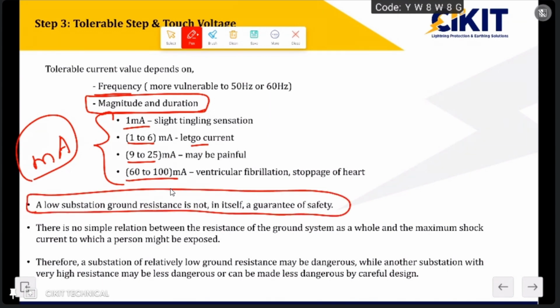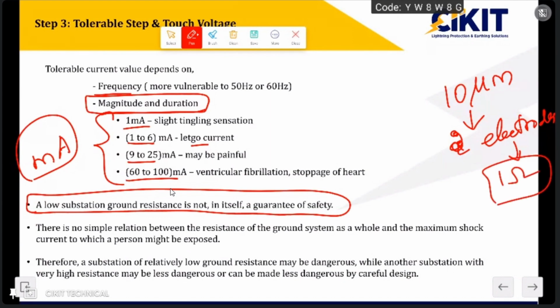For example, if I'm working with some substations, they will tell that if you provide two earth electrodes for body and two earth electrodes for neutral, that will be sufficient for the protection. If earth electrode resistance is the only parameter, and I'm working with site conditions having a resistivity of 10 ohm meter, then if I install only one or two earth electrodes, I can achieve a resistance value of 1 ohm. But whether these two earth electrodes are sufficient to maintain the step voltage and touch voltage, that is the question. Even if the resistance is less than 1 ohm, we cannot ensure that it is safe.